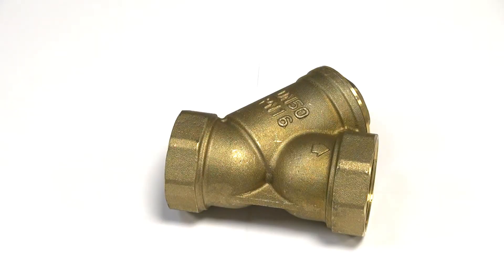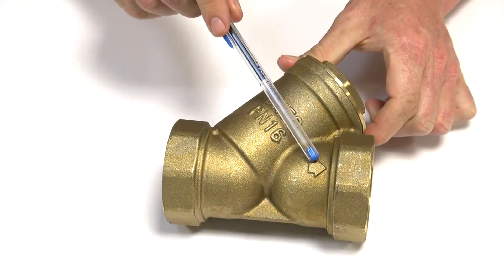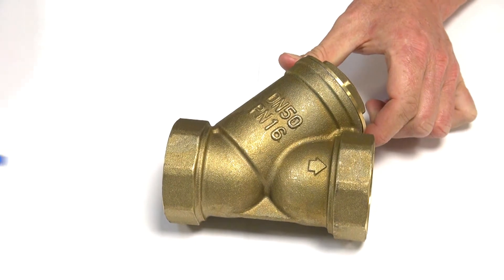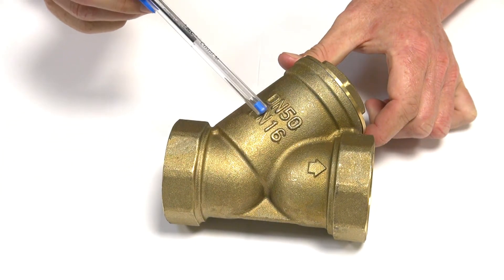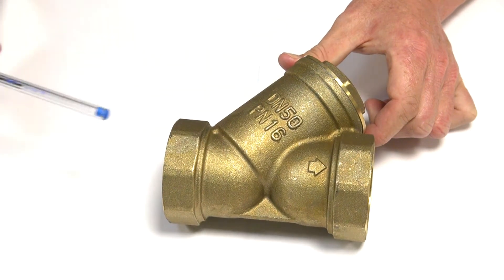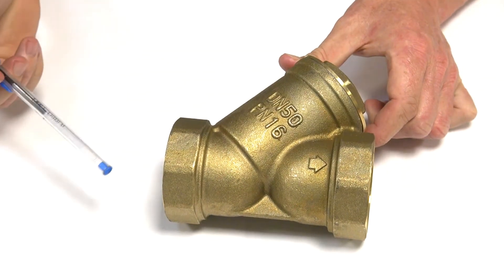Here we have a brass Y strainer. Things to note when installing is the arrow here, which represents the direction of flow. As long as your flow is going in this direction, it will come in this port here. This is where your Y strainer is — a stainless steel mesh on a 60-degree angle with one-millimeter holes. It will go through the strainer and out through there.